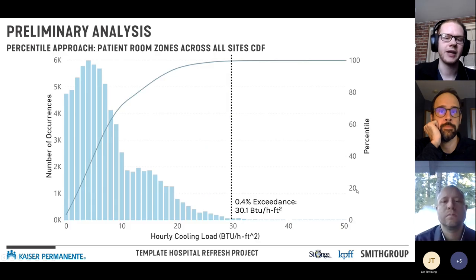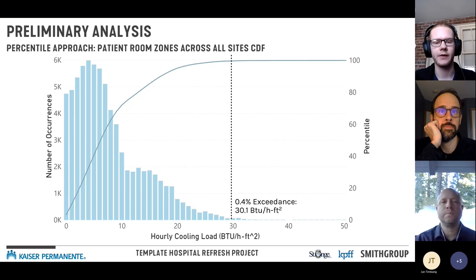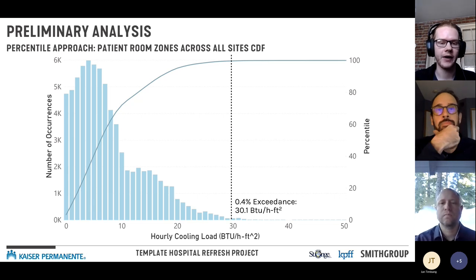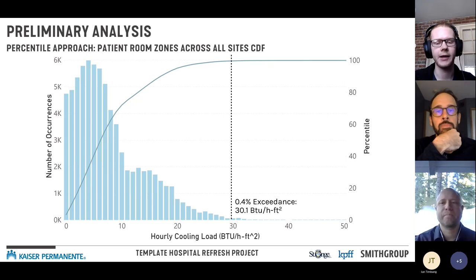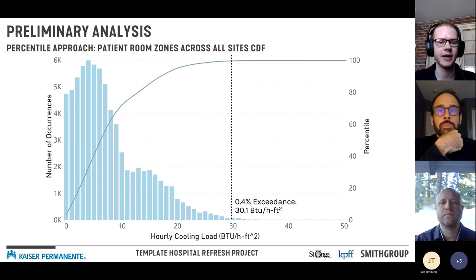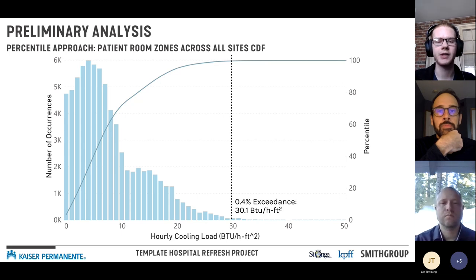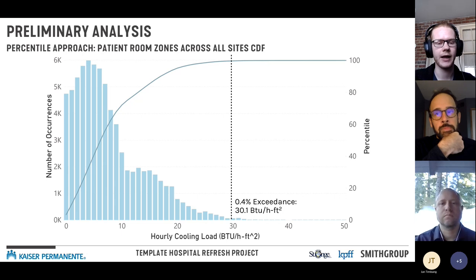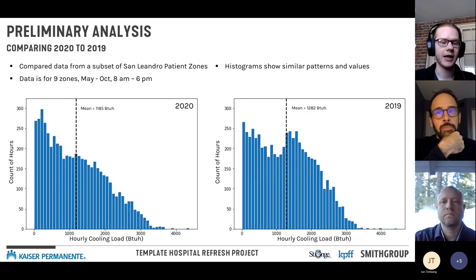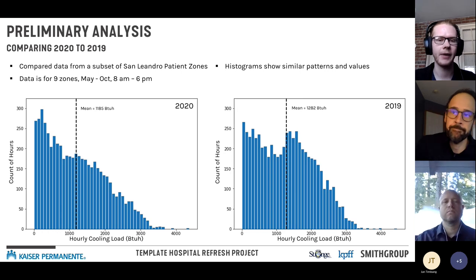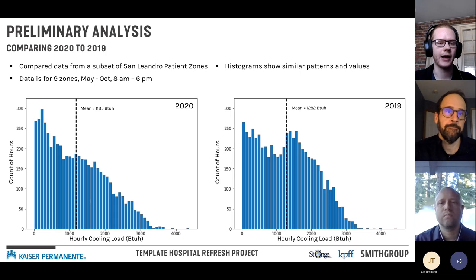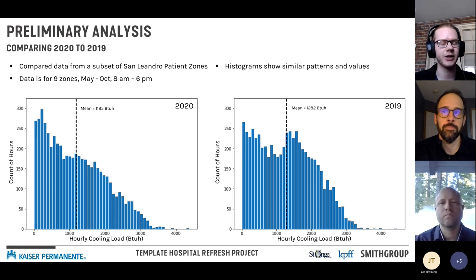For patient room data across all sites, plotting the CDF on top of a histogram shows that 30.1 BTU/h per sq ft is the 0.4% exceedance rate — meaning 99.6% of all patient room data we looked at is below that value. There were also questions from peer reviewers about 2020 being an abnormal year given COVID and how that might have impacted results.